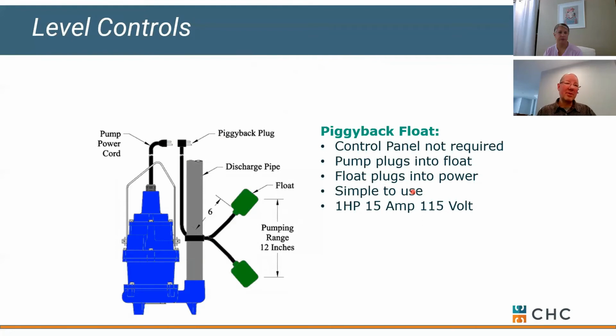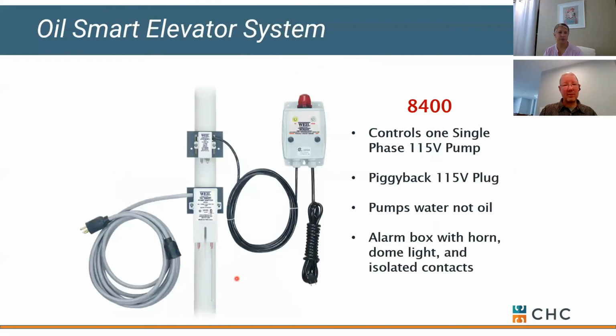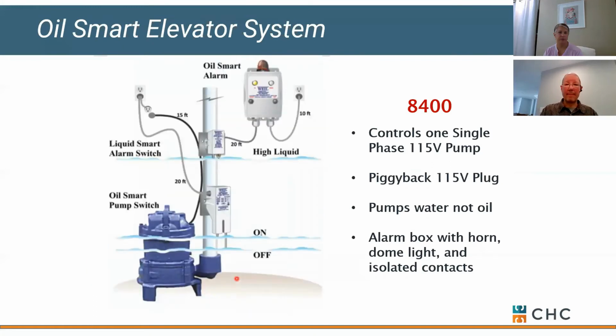For an elevator sump, you might end up with something we call a piggyback float. That's simply a float that will turn the pump on or off as it rises and falls. So it's really limited on the control panel there. You're just relying on float operation. You might also have a need for a probe type control, where you have potential for hydraulic oil in your elevator system to get pumped into sanitary. They don't like that. So this controls your pump operation based on oil in the basin. You could also use this for overall pump control. It's very compact. You don't have a float that swings. It's simply probes. So that's one option for you.